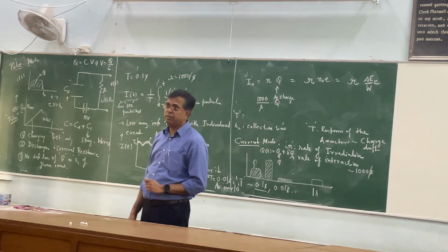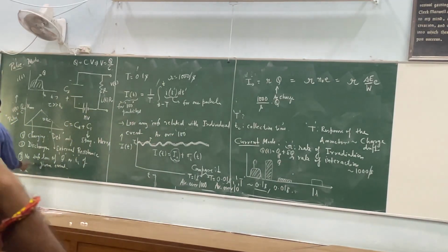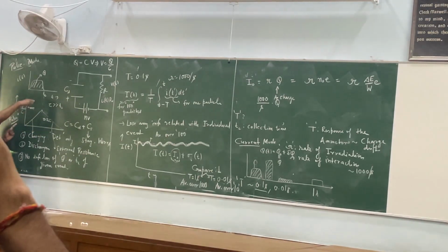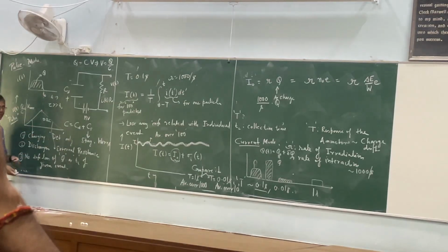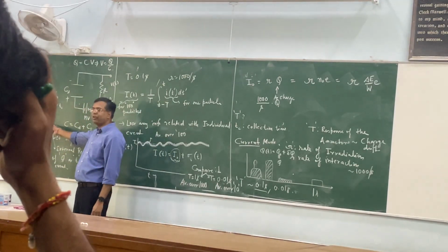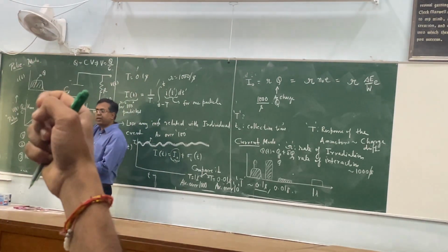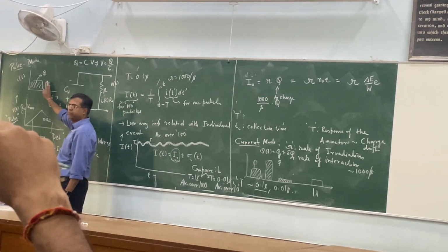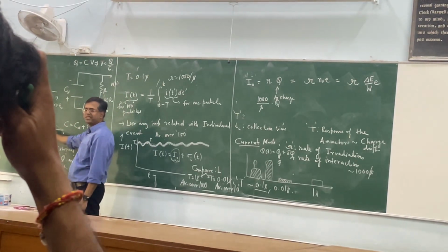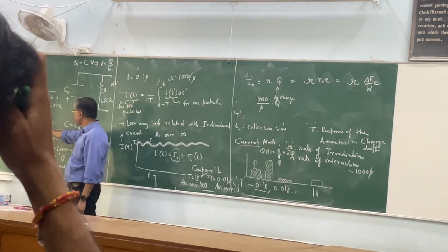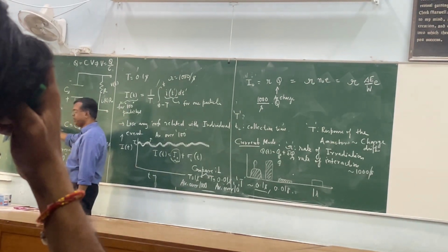So this no information loss means that in the pulse mode of counting, why am I calling it pulse? Because Vt is now changing with time. Earlier my average current was constant, right? Here we do not have any constant current. It's changing with time. Now if the next pulse comes here, then you see that my decay hasn't given you the complete zero. Suddenly, my system is not going back to its original zero voltage. I am not going to resolve that. Either I make my RC decay pretty fast, or otherwise I cannot resolve it.